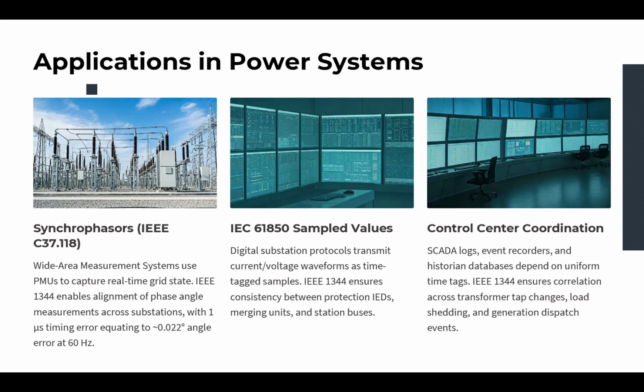The IEEE 1344 in that regard basically guarantees that the events from different stations can be sequenced without any ambiguity. And also the time correlation of alarms and control actions can be validated when you follow IEEE 1344 for the SCADA system data. And we can reliably replay the system states and run the analysis on an event that already happened, and we have it in our log history.